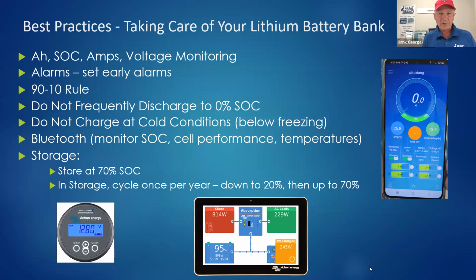So it's fine to discharge all the way down to 10%, and then just charge back up. Just don't stay down at 10% or lower. Go to zero, charge a little bit, then discharge some more, charge a little bit, discharge, so that you're not staying below 10%. And the same thing at the other end. You don't want to stay between 100% and 90%. Don't just keep charging everything all the time so you never get below 90%. It's better to let lithium discharge and charge it up, let it discharge, even if only partially. So I'm not saying you have to discharge all the way to 10%, but if, let's say, you're at 90% and you discharge to 80% and then charge it up to 90, that's fine. These batteries will take that all day. It's not a problem. So use it as a convenience, wherever it's convenient, charge, but periodically, every 2 weeks or so while you're cruising, charge it all the way up to full, all the way up to float.